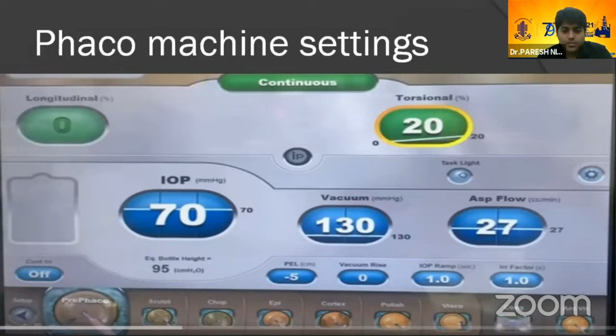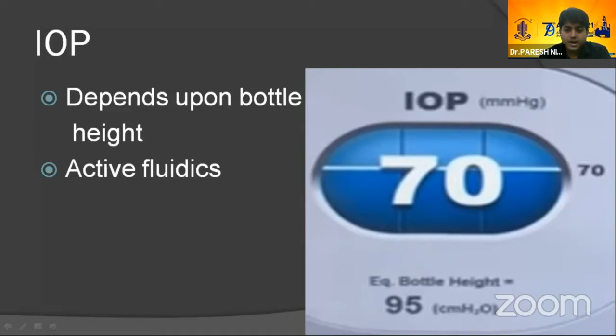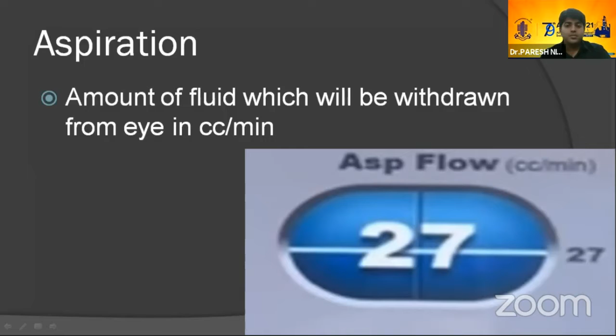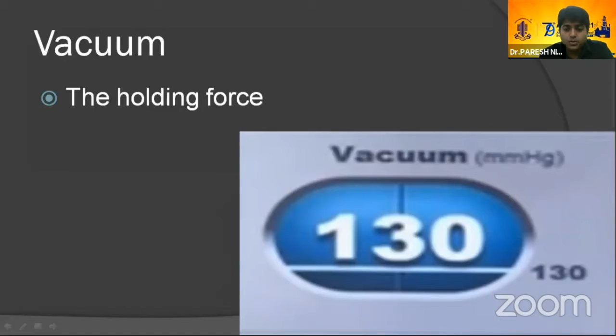Talking about the basic phaco setting, I'll be discussing about the peristaltic machine. Basically, we have power. We can set power. The IOP is dependent on the bottle height or the irrigation pressure as in active fluidics. The aspiration can be set. It is basically the cc per minute withdrawal of BSS from the eye. And the vacuum, it is the holding force which we get.